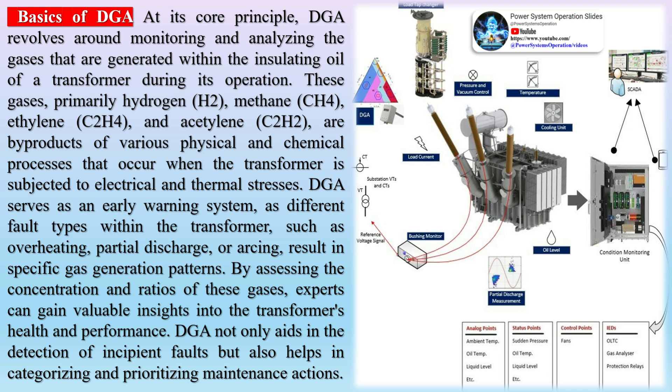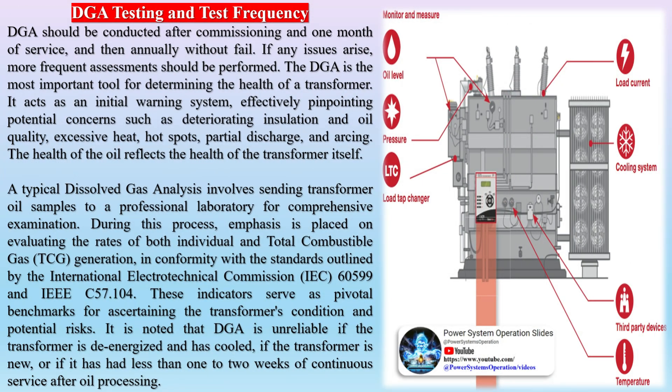It's an effective method that detects hydrogen generation levels inside a transformer's main tank. Hydrogen generation occurs when thermal levels are above a transformer's normal operating temperature. Monitoring for key gas provides an early indication of most abnormal operating conditions that may occur in the main tank. A major failure on a transformer is defined as an incident that takes the transformer out of service for seven or more days.